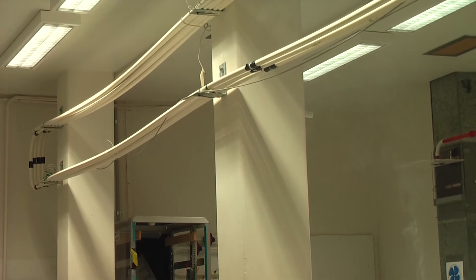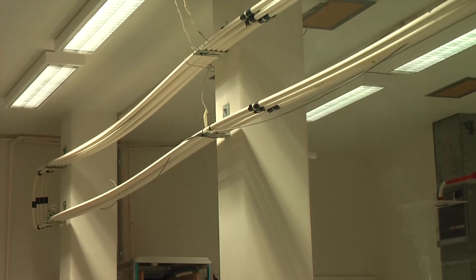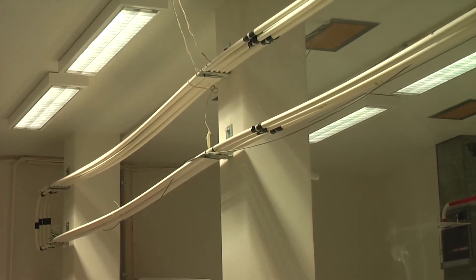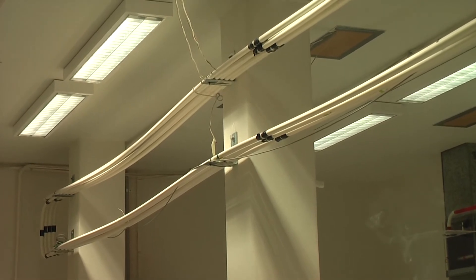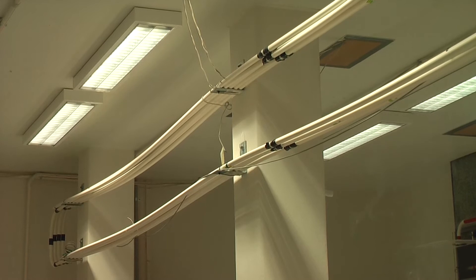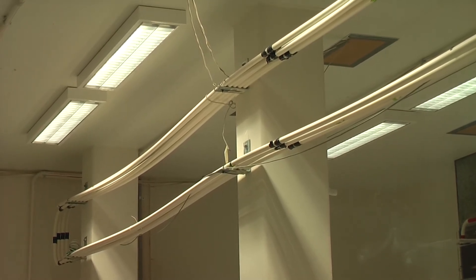We are one minute into the test. None of the detection systems have registered a fire event. This is a very slow smouldering event, as you can see.